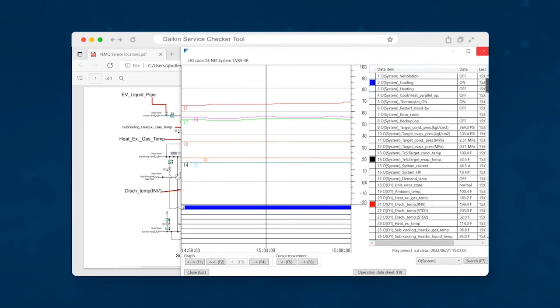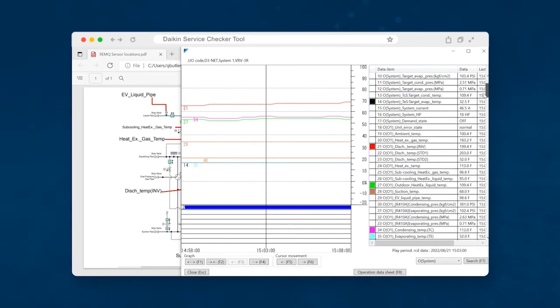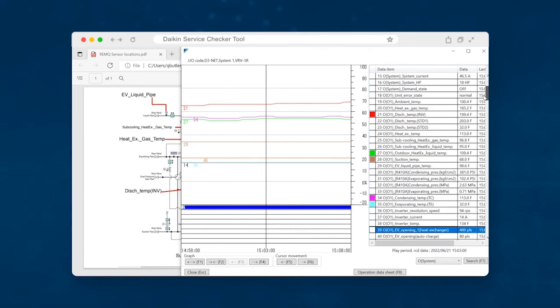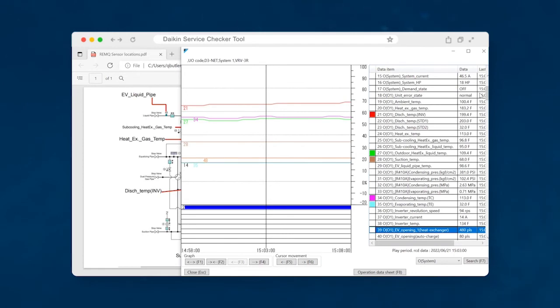Do you remember how low this charge was? We actually haven't got approval to go recover the charge on this one yet. But this is one that we've got to quote out to do a refrigerant recovery on it and pressure test the system with nitrogen and find out where the leaks are. If you do find a leak, the best practice is always recover all the gas. Absolutely. Know exactly what you're dealing with. Pull it into a vacuum and then recharge it with the calculated amount of refrigerant.